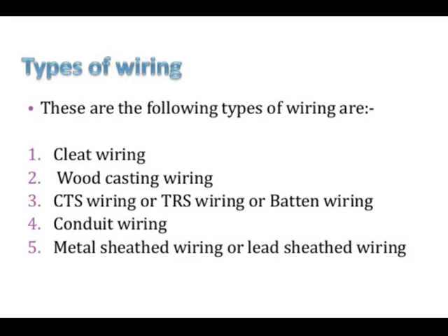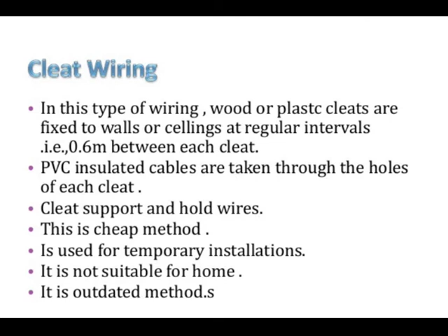In this type of wiring, wooden or plastic cleats are fixed to walls or ceilings at regular intervals, approximately 0.6 meter between each cleat, and PVC insulated cables are taken through the holes of each cleat, and the cleats support and hold the wires. This is a cheap method. It is used for temporary installations. It is not suitable for home because the wires remain open. It is an outdated method because a number of advantageous methods are introduced today.